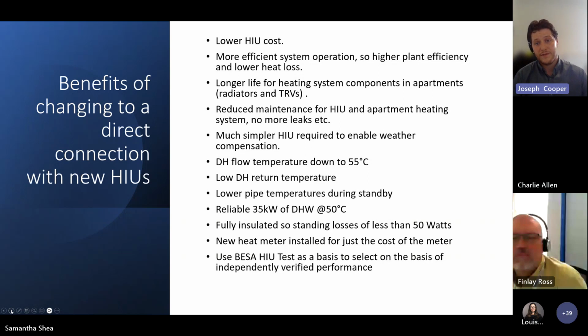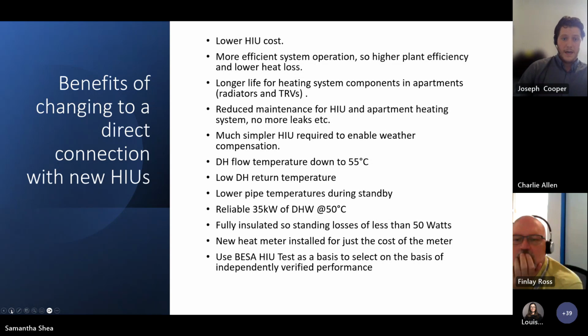It would bring the district heat flow temperature down to 55 degrees, allow us to lower the return and pipe temperatures, and give us a reliable 35 kilowatts of domestic hot water at 50 degrees Celsius. The new HIUs will also be fully insulated, unlike what's currently in situ, so standing losses would be less than 50 watts.